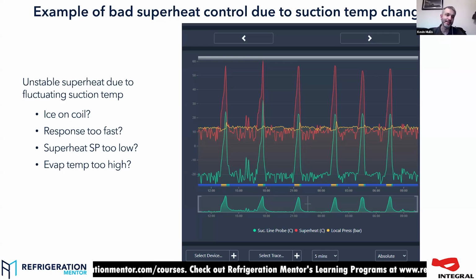RDM has the facility to shut the valve if it detects a superheat problem. You set the temperature at which it sees that superheat issue, and you can tell it, once you see that issue, how much do you want me to open the valve? And you can tell that to be 0. In fact, there's a good reason, if you're using a transducer especially, to tell it, if you see a problem, go to 0, because it'll then sit there for a little while to let the coil recover, and then it'll have another go. It'll go back into start, and it will try again.